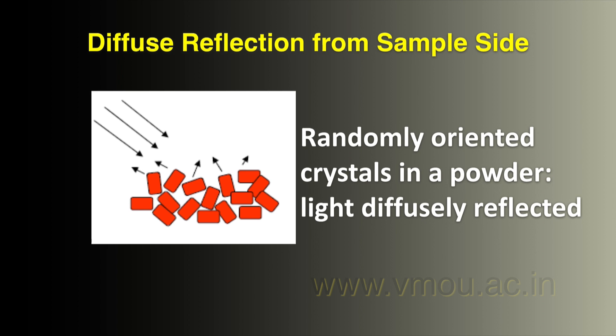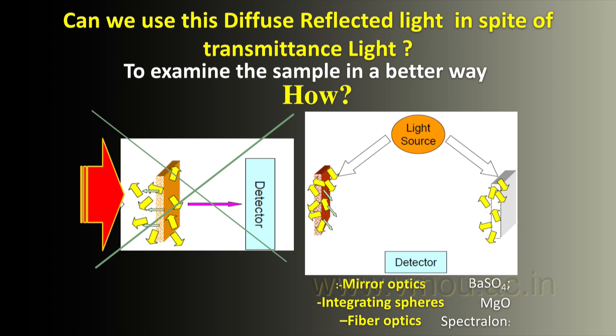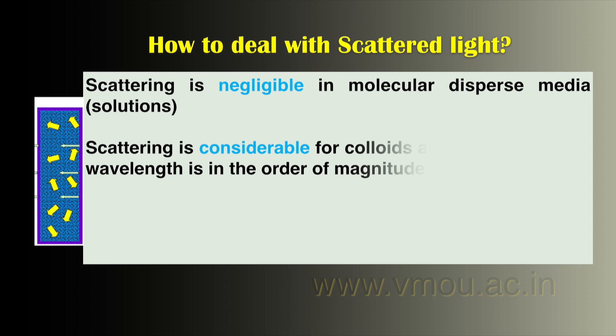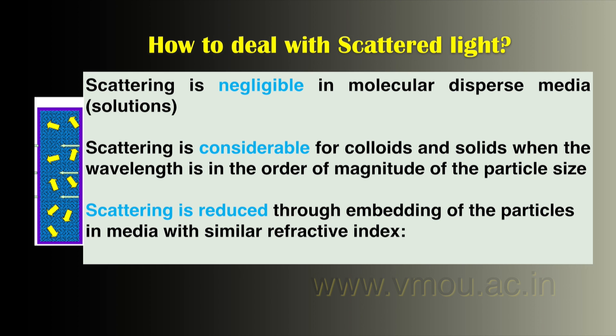This is the diffuse reflectance sample slide, where crystals in a powder diffusely reflect light. The first approach uses the sample directly in solution or gas form, but it is not used for solid cases. Therefore, the second technique uses a white reference sample alongside the analysis sample; we subtract the reference material's absorbance and then obtain the sample's analysis. Scattered light is negligible in molecularly dispersed media, but scattering is significant for colloidal or solid materials when wavelength is on the order of particle size. Scattering can be reduced by embedding particles in media with a similar refractive index, using barium sulfate or magnesium oxide as reference materials.